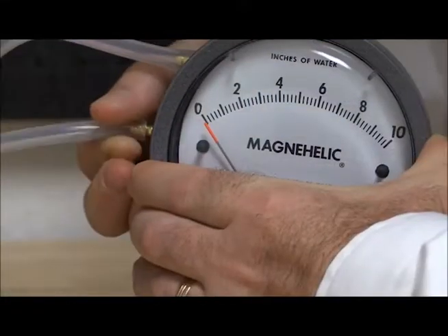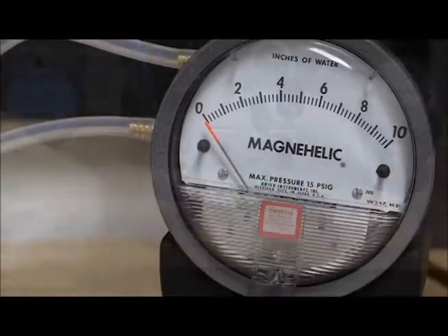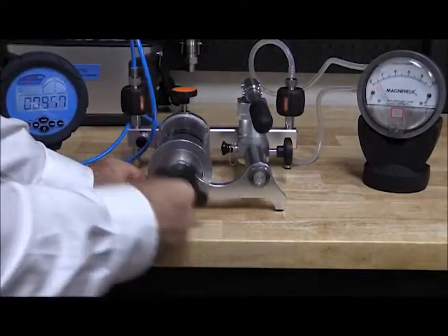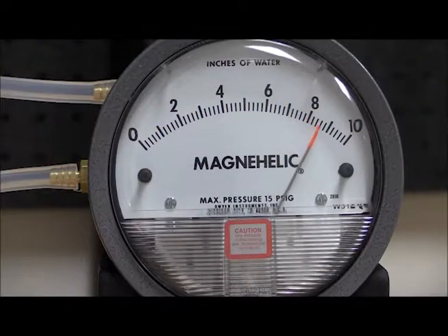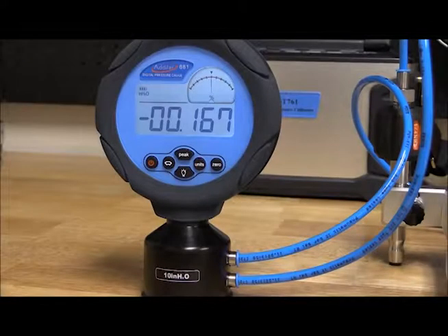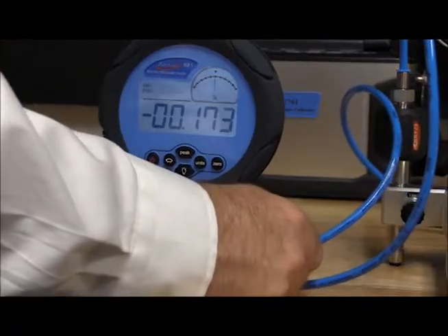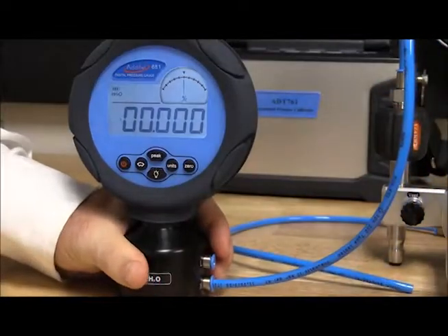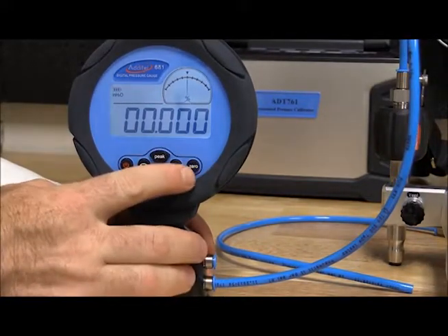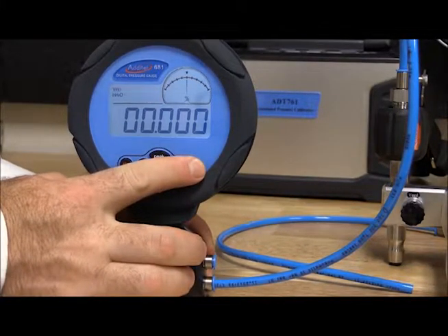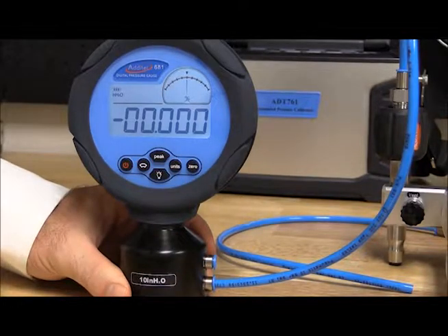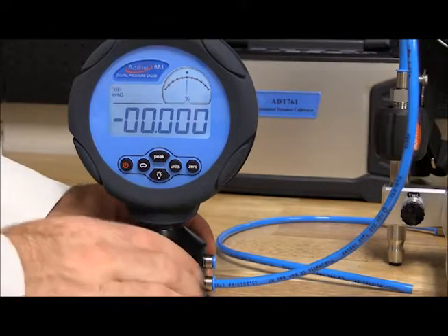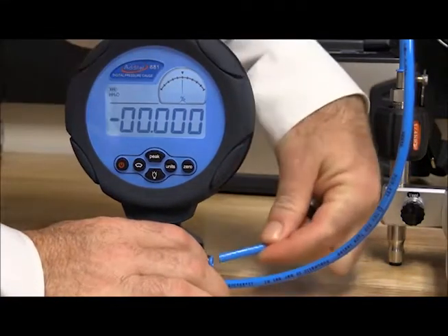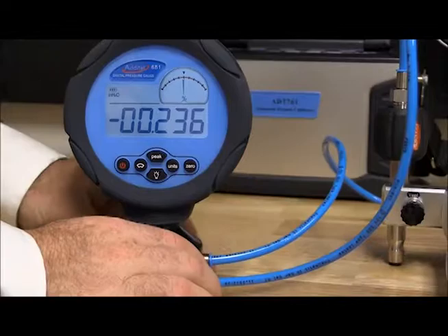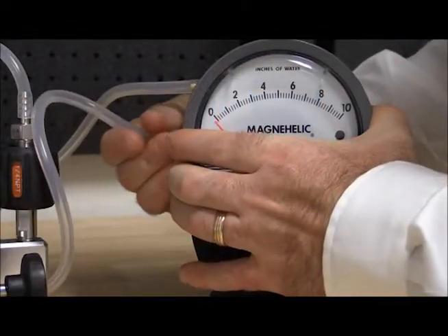Just like the previous example, the DUT orientation is still important. We will exercise the gauge a few times before starting the calibration. Recording the 0 point may vary depending on the type of DUT. If the DUT is a digital gauge, then keep the reference gauge and the DUT reference ports connected together and zero both gauges. In this example, I have an analog gauge, so I'll disconnect both the reference ports and leave them open to atmosphere to zero the 681 reference gauge. After recording the 0, we will connect both reference ports together and proceed through the calibration.